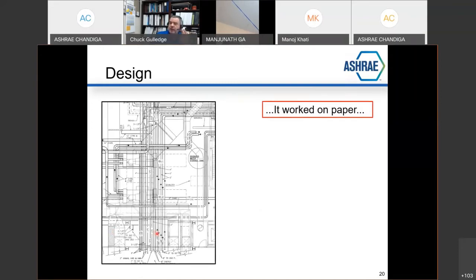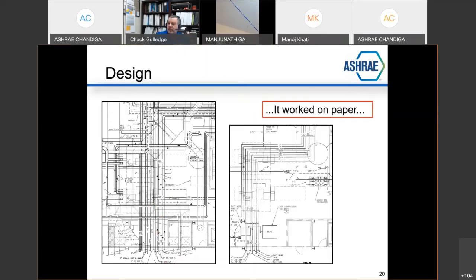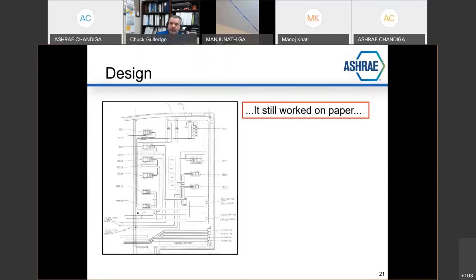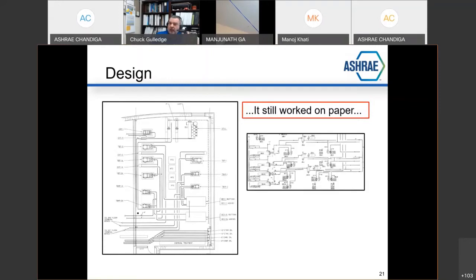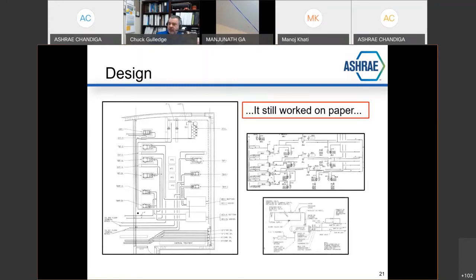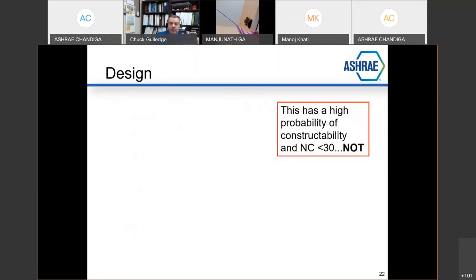Tell me how you can possibly build something in a 2D scenario with a static drawing with all of these big pipe sizes, 8-inch, 5-inch, 5-inch, 4-inch, all layered as single line, layered on top of more layers of other pipes sitting on top of it. And oh, by the way, there's another layer on top of that in single line fashion, with more details provided on the hookups at the scenarios and then some more typical details. This is a huge disconnect that ties us to that dance of the silos where we don't demonstrate constructability and communicate how something can actually be built. We just put stuff on paper and throw it out there and try to let the contractors figure it out in the field. This is a horrible approach to doing things.